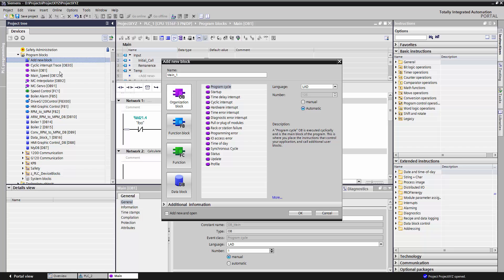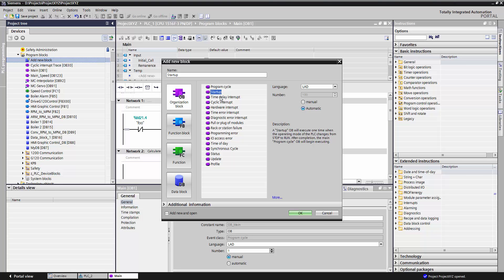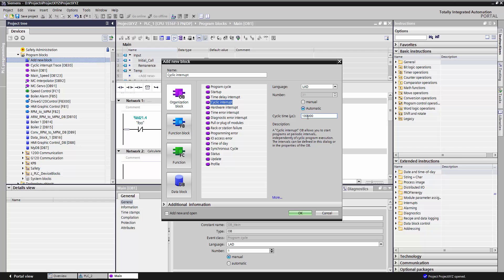and its execution time depends solely on the code that it is running. Other OBs include the startup task, which is run once when the PLC goes from stop mode to run mode. The cyclic interrupt, which will run every time this cyclic timer elapses.